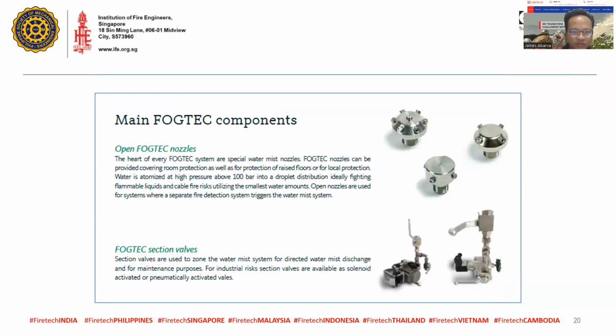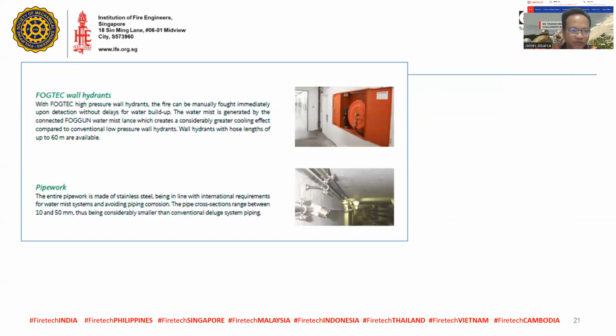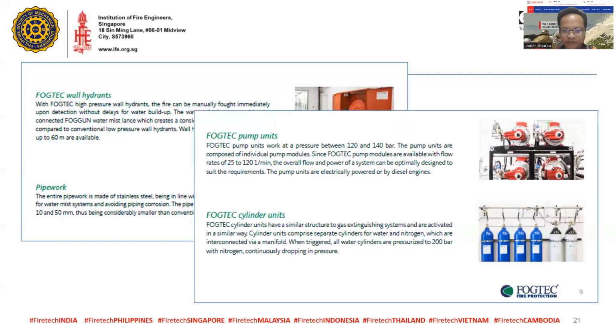So these are the components of the water mist system. You have your nozzles, you have your section valves. Section valves can act like your deluge valve or sprinkler alarm valve by principle, and you have your wall hydrants, you have your pipe work. As I mentioned a while ago, you will have only 2 inch and 10 mm as the smallest one. So imagine that's the only diameter of pipe running in your whole building, in your power plant. And I believe that's a big space savings on the part of the owner or the occupants.